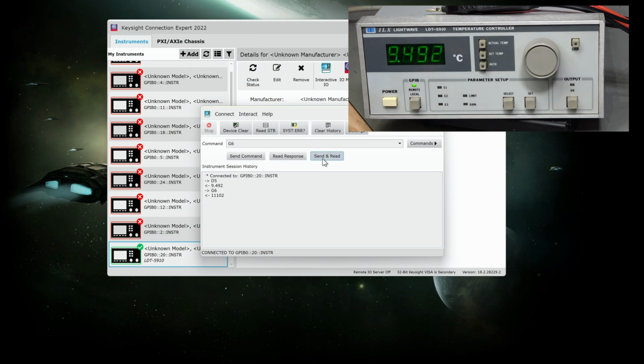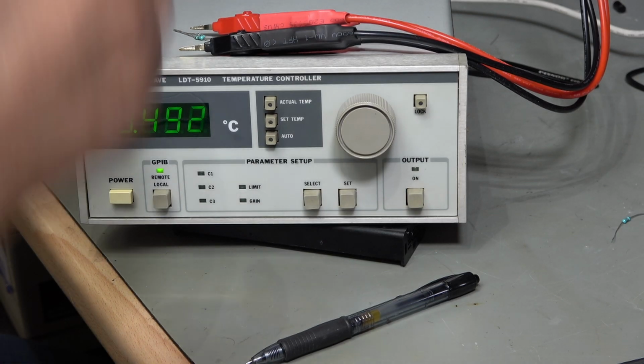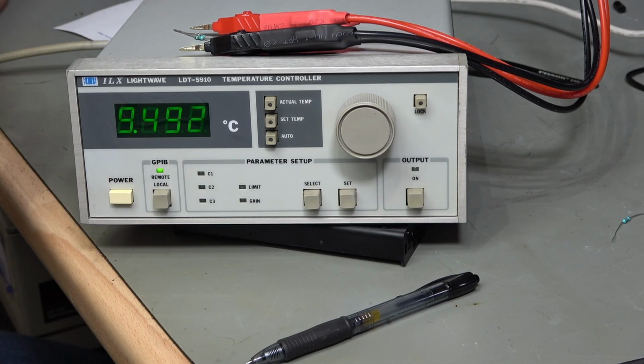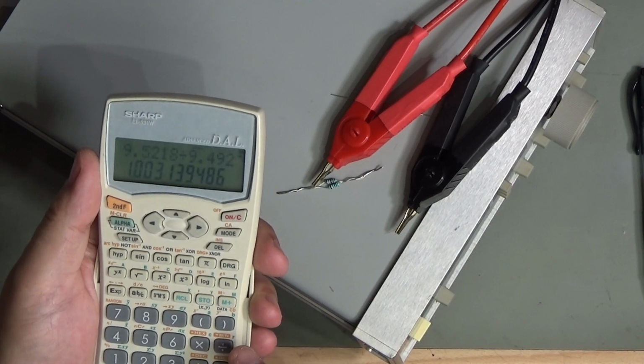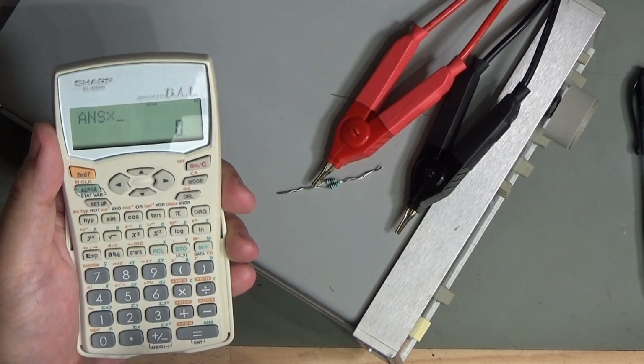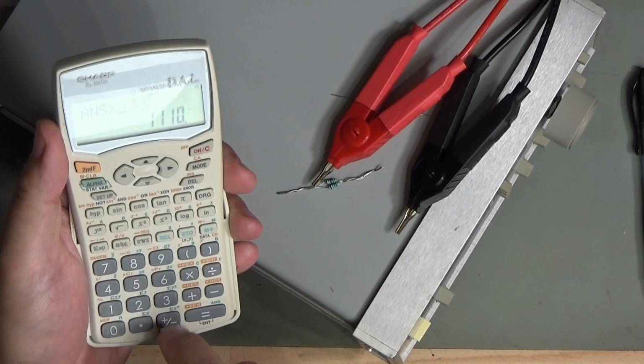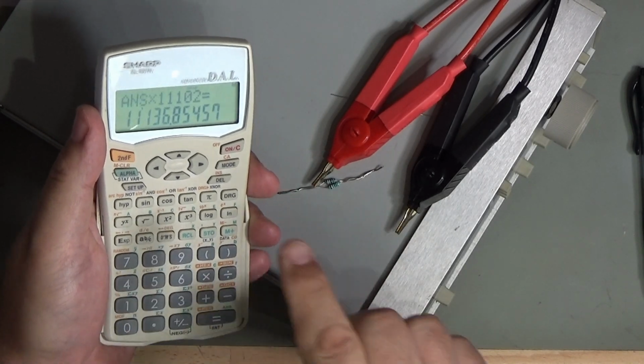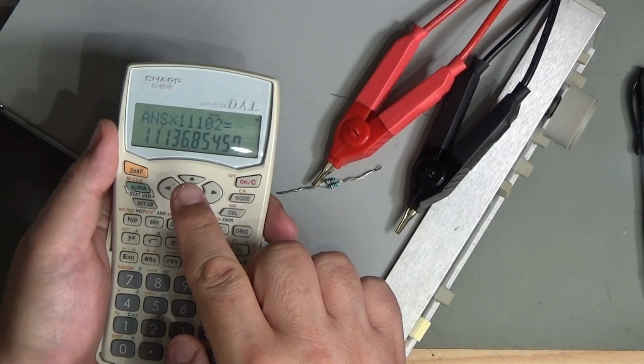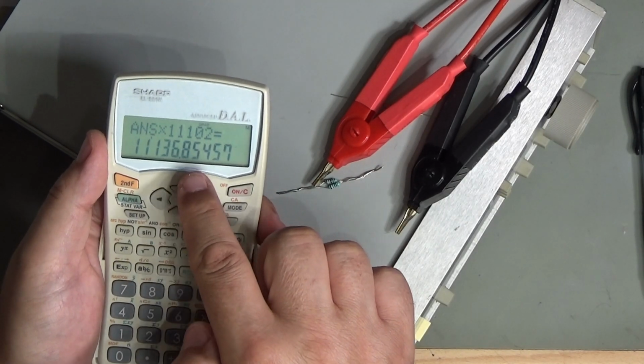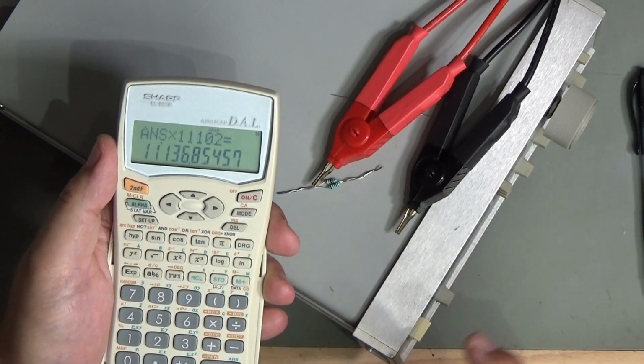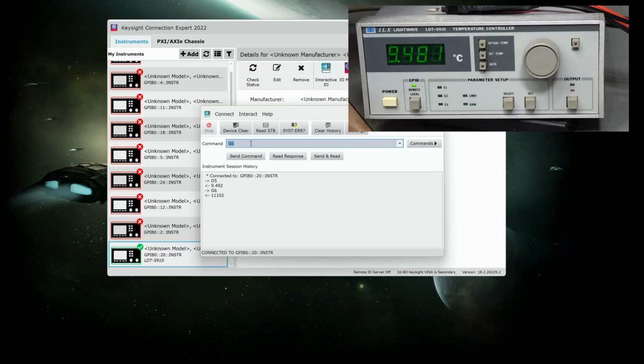send receive, and that returns 11102 as the number that it's internally multiplying everything by in order to get that 9.492. So I need to increase that, so I take my calculator value that I've just worked out and times 11102. So that tells me that I need to input 11136.9, so 11137. So I do numeric value n 11137. I need to put that value into position 6 because I've got it from position 6. So let's do a send and receive now.